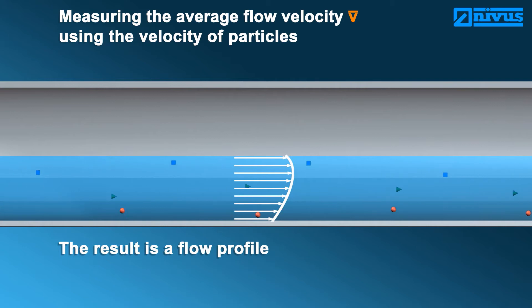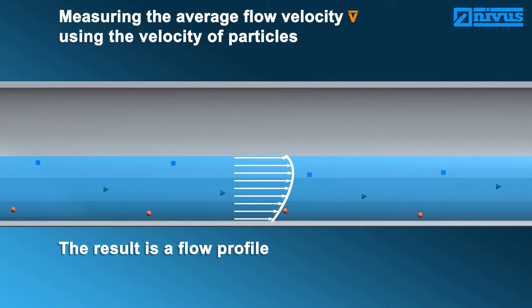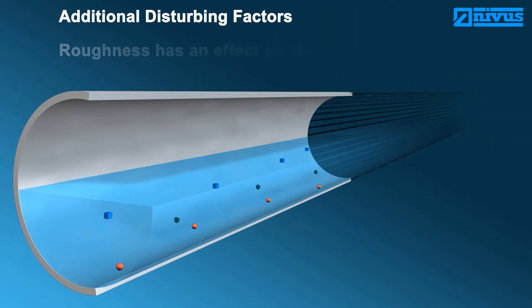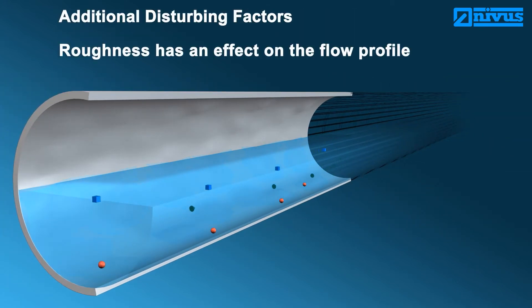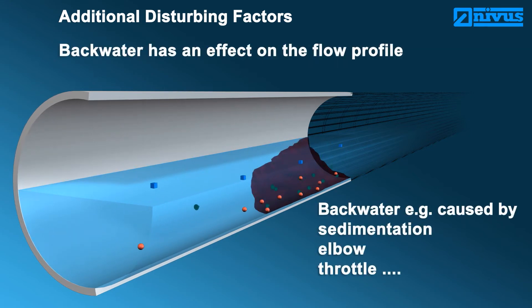This profile depicts the flow velocities related to the levels. Miscellaneous factors affect this flow profile — disturbing free discharge or may result in the formation of backwater. Such disturbing factors may be pipe roughness and varying sedimentation, solid concentration, or influences due to construction such as elbows and throttle equipment.